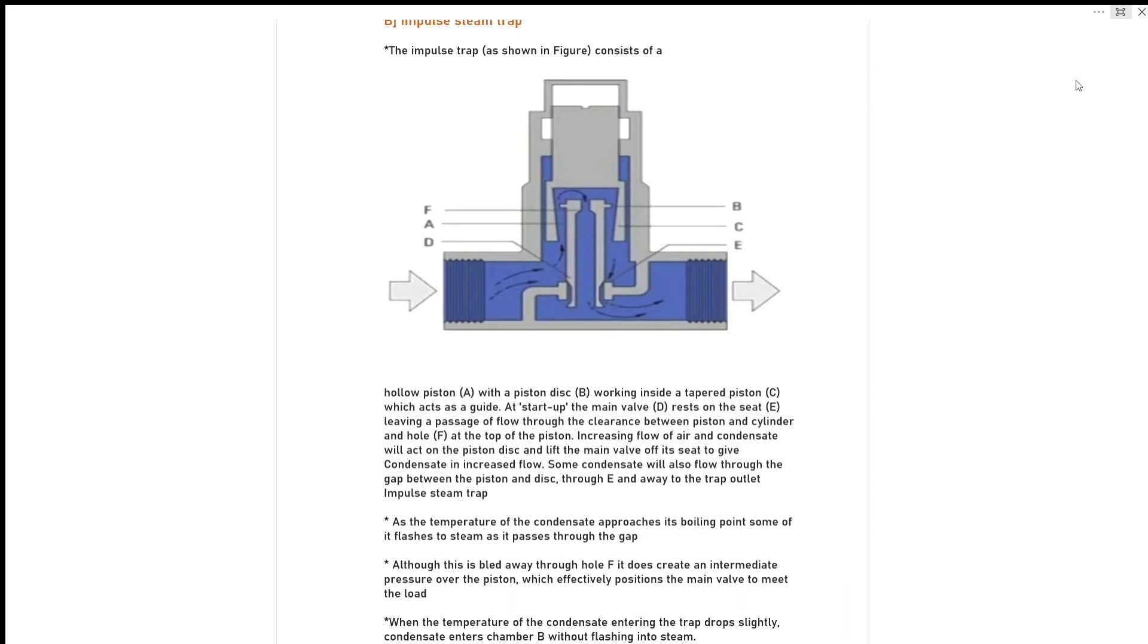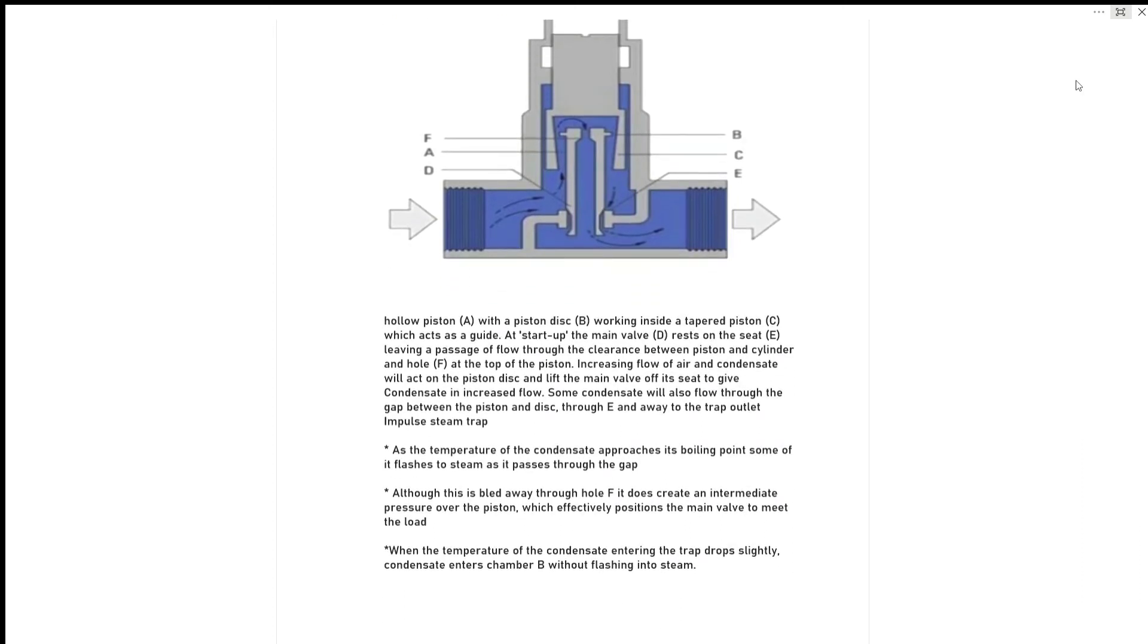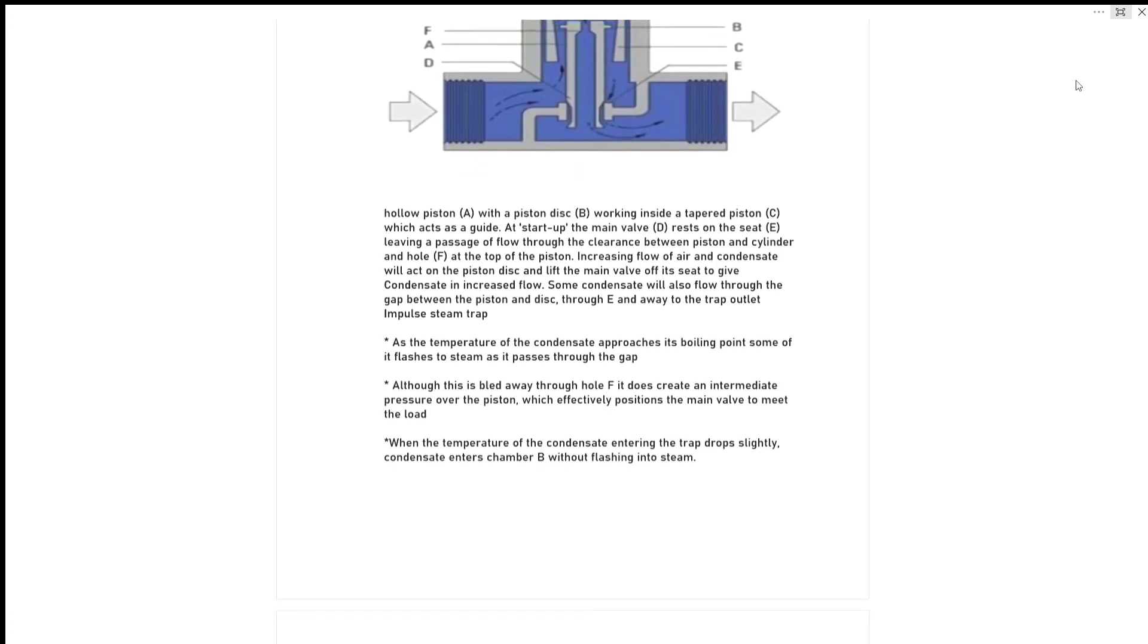As the temperature of condensate approaches its boiling point, some of it flashes to steam as it passes through the gap. Although this is bled away through hole F, it does create an intermediate pressure over the piston which effectively positions the main valve to meet the load.